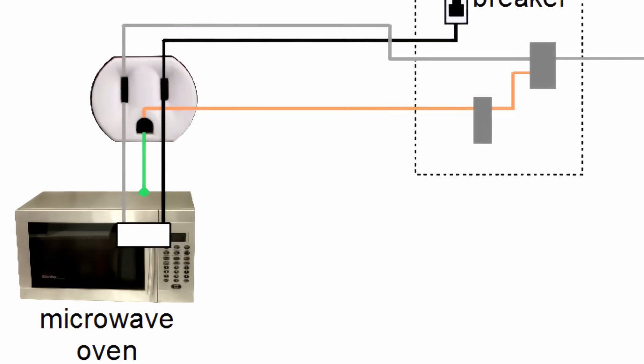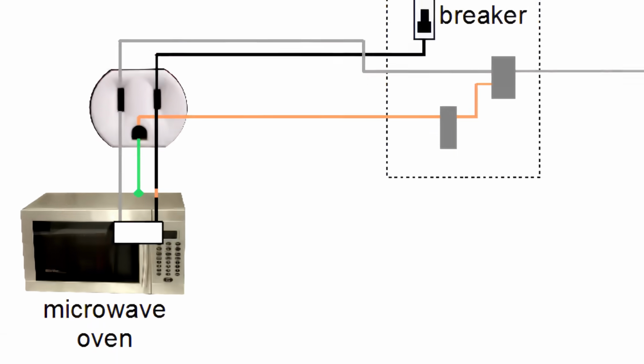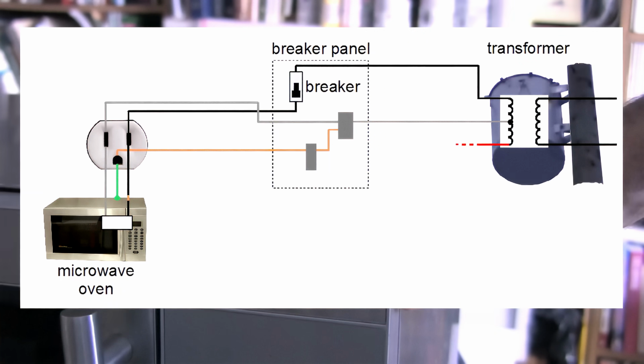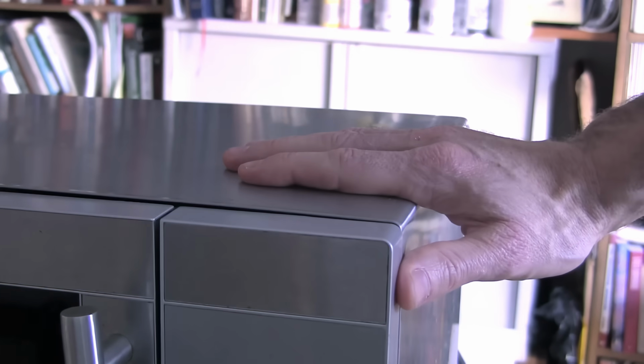The problem starts when the insulation on the hot wire breaks, and the wire touches the microwave oven's case. Since the case is connected to the ground wire, we now have this complete circuit along the ground wire to the breaker panel, then along the neutral wire onward to the transformer on the pole, through the transformer's coil, back through the hot, through the breaker, and continuing to the hot in the microwave oven, where it's touching the case. There's very little resistance along that circuit, and so the electrical current will be very high, high enough to trip the breaker, which opens the circuit, making it safe to touch the microwave oven's case again.